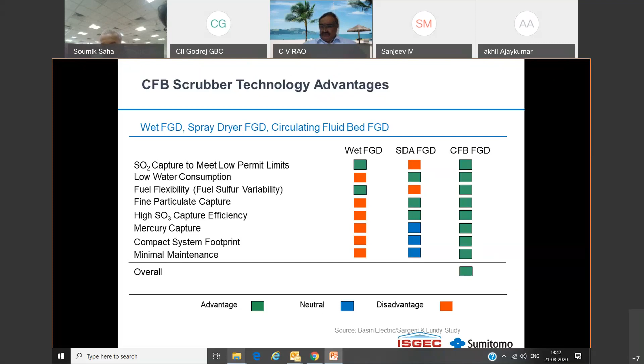Also, I would like to add that in this system, unlike wet FGD, a wet stack is not required. So you do not need any modification in the existing chimney, or to add any wet stack. You just have to install the FGD and can have the existing stack running as it is. So this is what we have explained. This is the CFB scrubber where solids are getting recirculated. This scrubber is designed in such a way that we get around 4 to 6 seconds residence time, which is good enough for proper reaction of the flue gas.